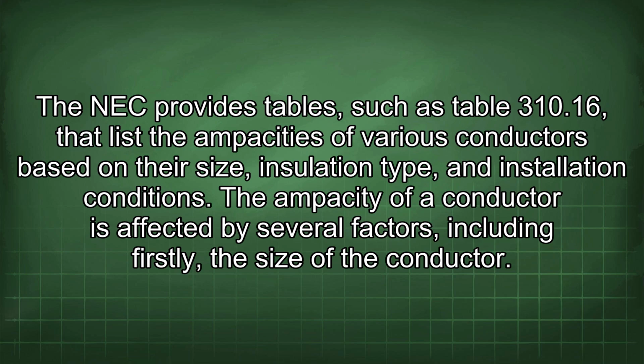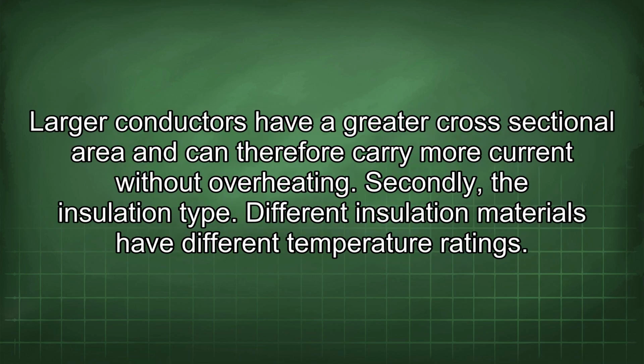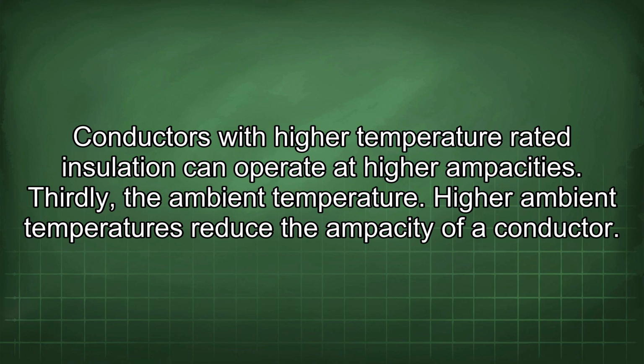type, and installation conditions. The ampacity of a conductor is affected by several factors, including firstly, the size of the conductor. Larger conductors have a greater cross-sectional area and can therefore carry more current without overheating. Secondly, the insulation type. Different insulation materials have different temperature ratings. Conductors with higher temperature-rated insulation can operate at higher ampacities. Thirdly, the ambient temperature. Higher ambient temperatures reduce the ampacity of a conductor.